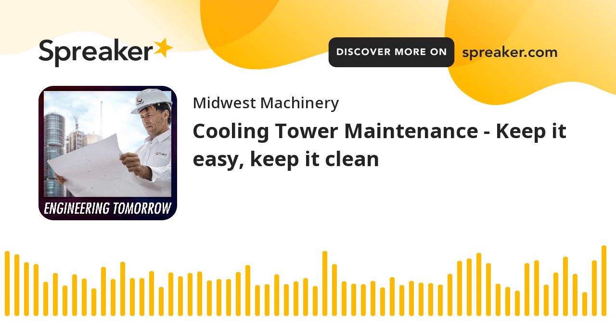Okay. So there are a couple other things that you need to do to maintain your tower. Now, a lot of people don't have a need for their cooling tower in the winter. This is typical in HVAC operation. You're not needing cooling, so you can shut off your cooling tower. And when you do this, you need to make sure that you drain your cooling tower, that you don't have that water in there so it would freeze and cause any damage. And there's a couple things that you also need to do if it were to have water in the tower during the winter.